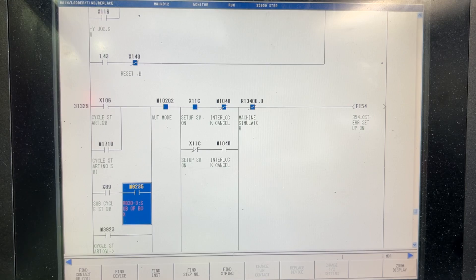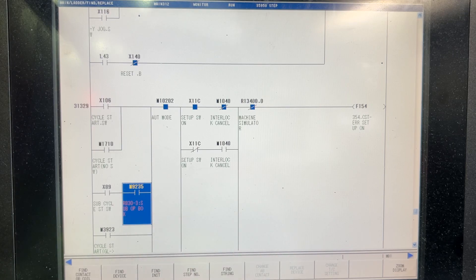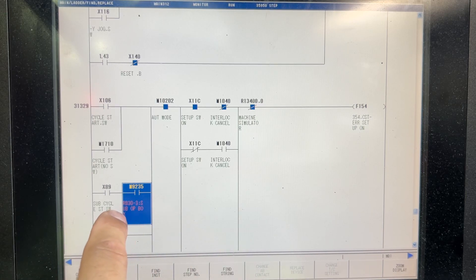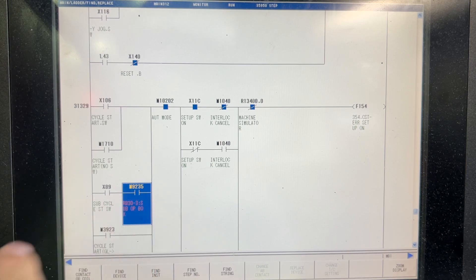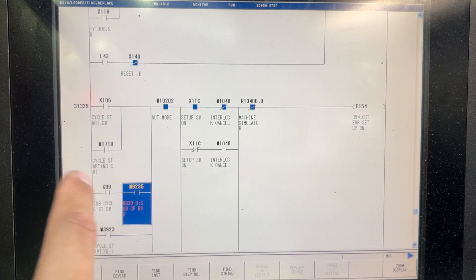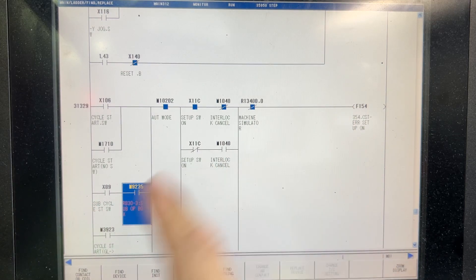What MESA does is to have PLC parameters to configure the ladder logic for different machines. In this case, if we enable RP30.3 and if we have the input X89, it's going to trigger the alarm.